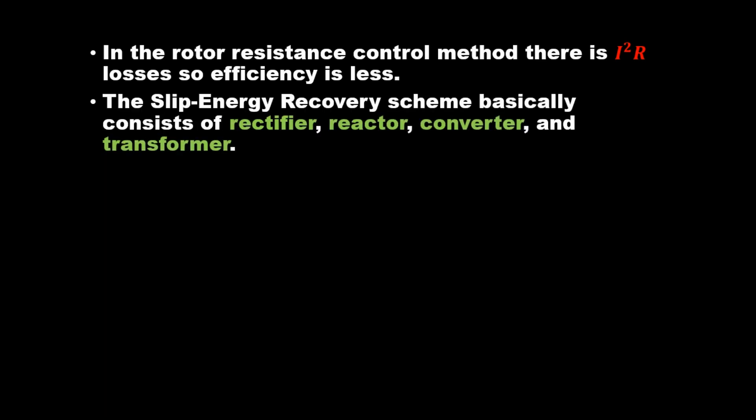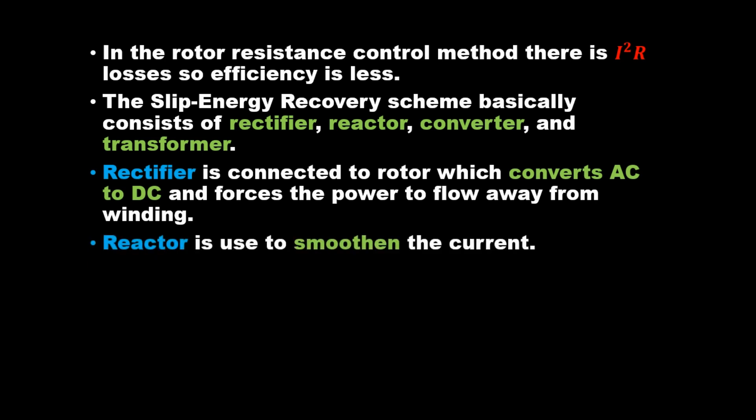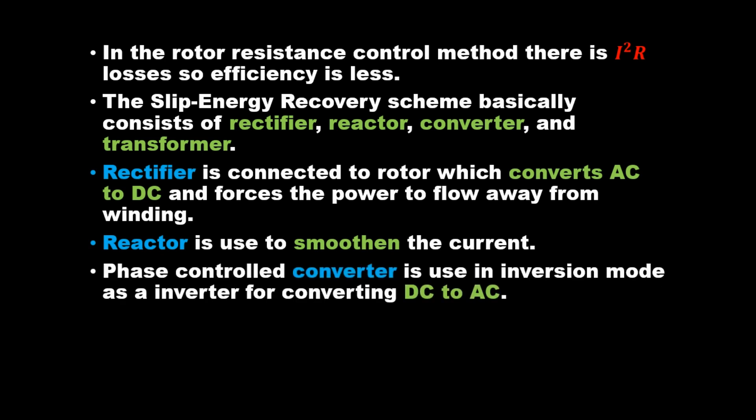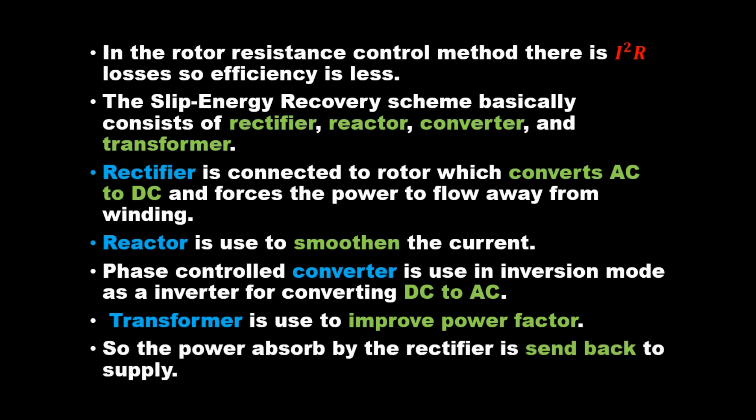The slip energy recovery scheme consists of a rectifier, reactor, converter, and transformer. The rectifier is connected to the rotor and converts AC to DC, forcing power to flow away from the winding. The reactor smoothens the current. The phase-controlled converter operates as an inverter, converting DC back to AC. The transformer improves power factor. So the power absorbed by the rectifier is sent back to the supply.